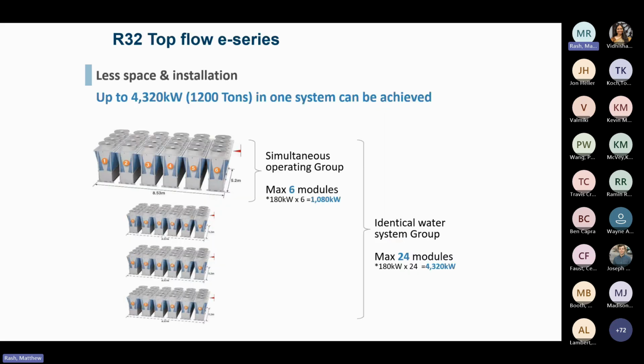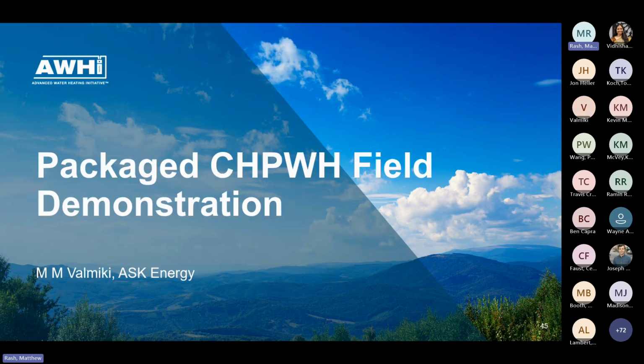So again, it's a modularized concept, all inverter driven scroll compressors. It actually has 4 circuits in it, and the unit can continue to run if one of those circuits goes down, so minimal impact. It also has built-in lead lag functionality like the CHV system, and you can actually scale this up with basic city multi controls to control to blended combined leaving water temperature with up to 24 modules. And again, the system will manage that automatically without additional DDC controls.